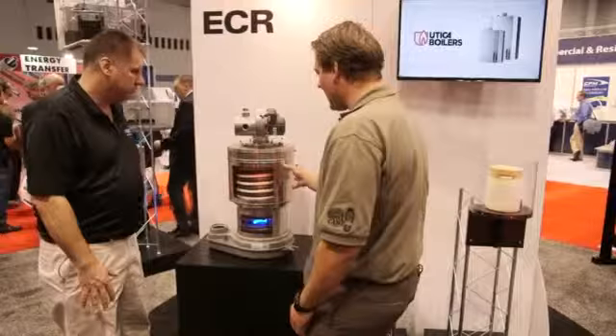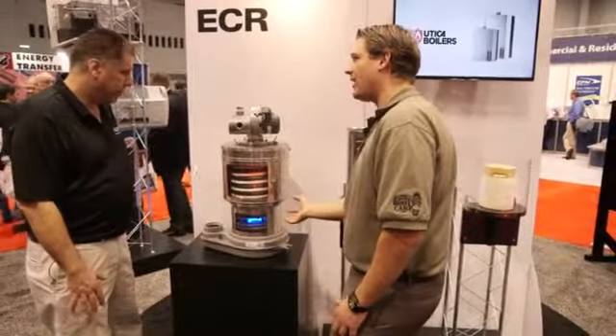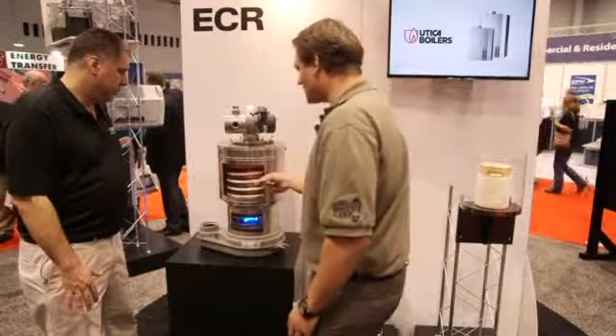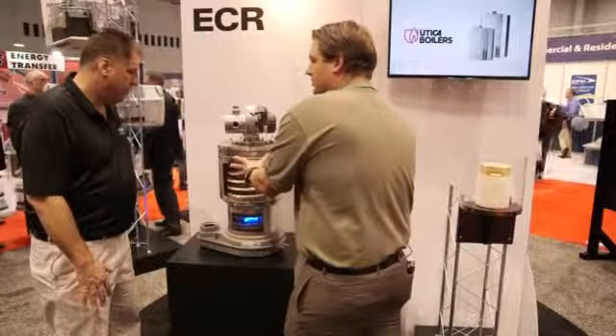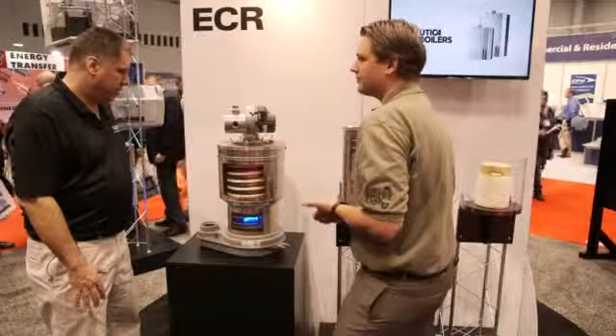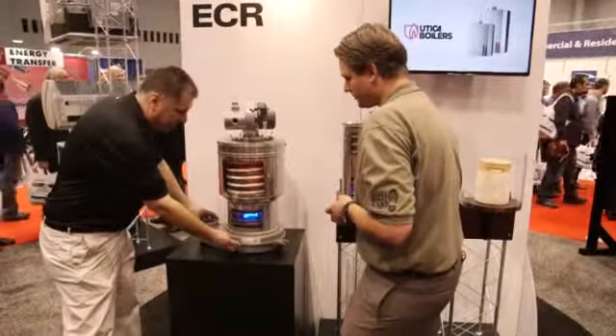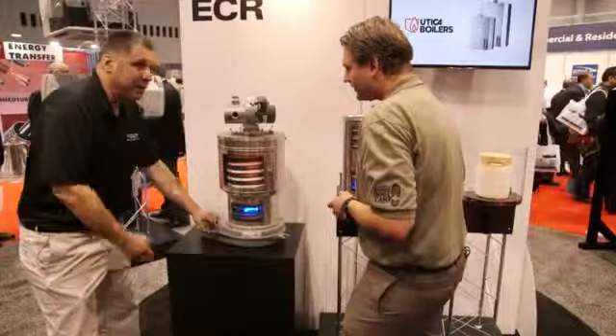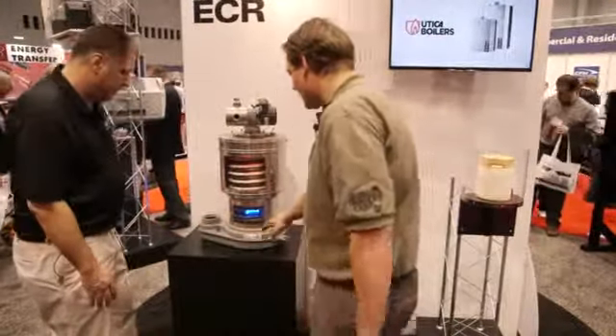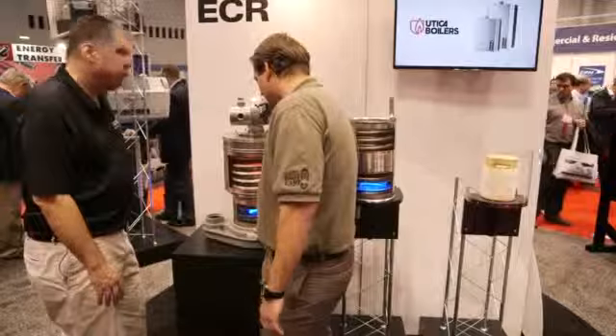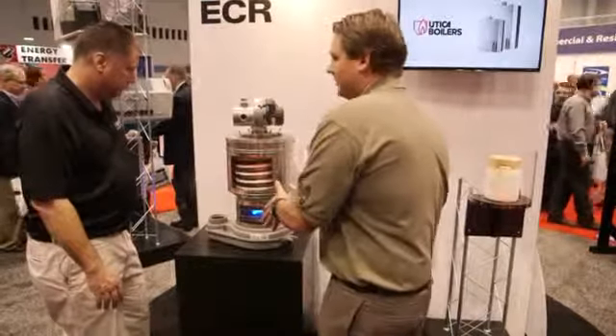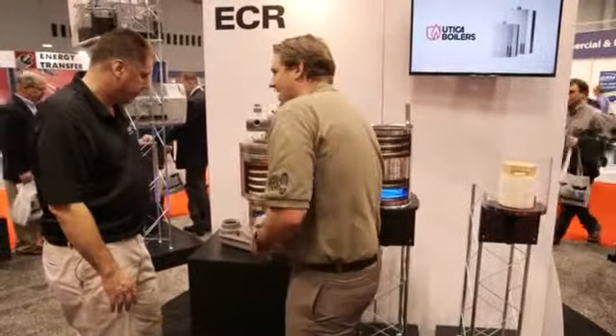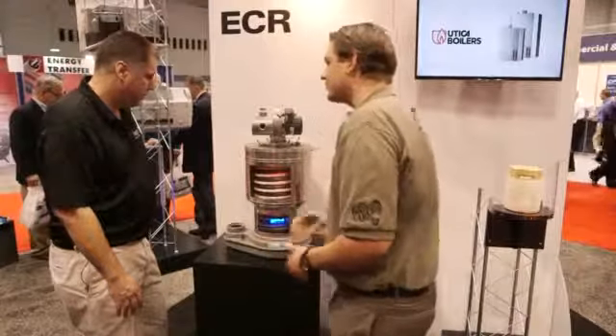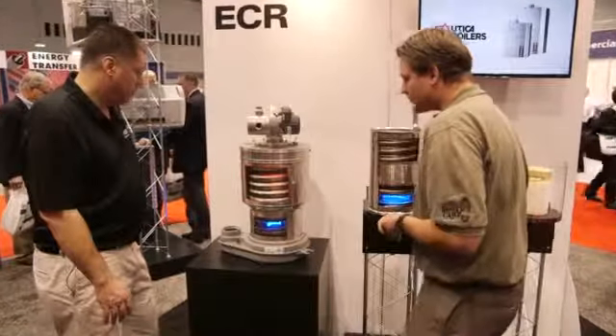It's a little bit taller, and you have this dual diameter can around it. That creates more turbulence inside of this. You get more heat absorption up top in the heat exchanger. Right. I noticed that the housing at the bottom of the collector box is some type of plastic. Talk to me about this. Yeah, we actually went with a polypropylene flue collector down here, and the heat exchanger sits down inside of it, which helps with the water flow, the way the condensate goes in. Its directional flow is corrected.